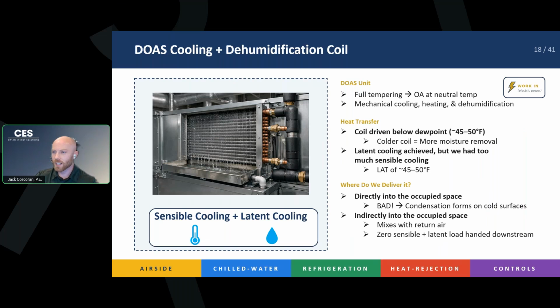So this dehumidification coil is super, super cold because we want to get rid of all that moisture. And we actually end up overcooling it sensibly just because we're trying to do so much latent removal. And again, right, this is our mechanical cooling. In the top right, we see we've got to put work in. This is not a free step, but it allows you to get those super tight humidity requirements that you have in a lot of spaces.